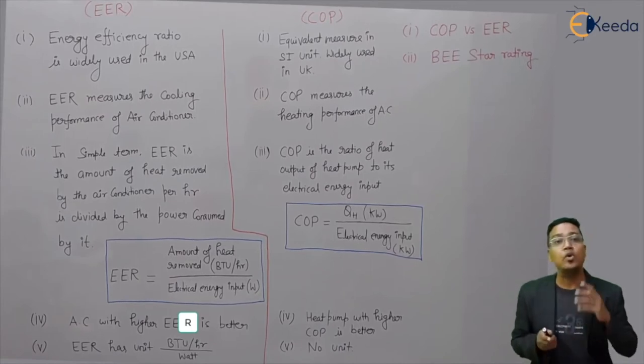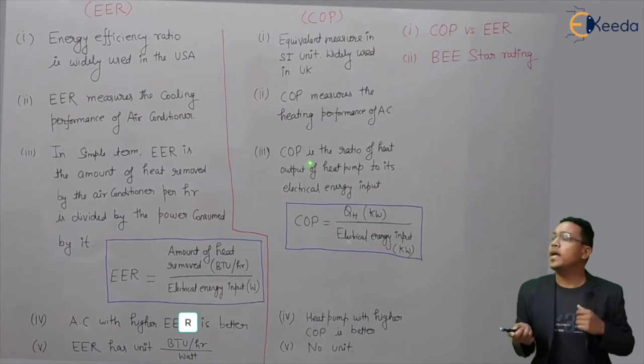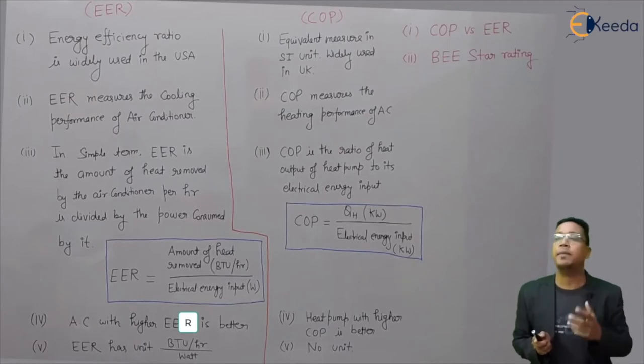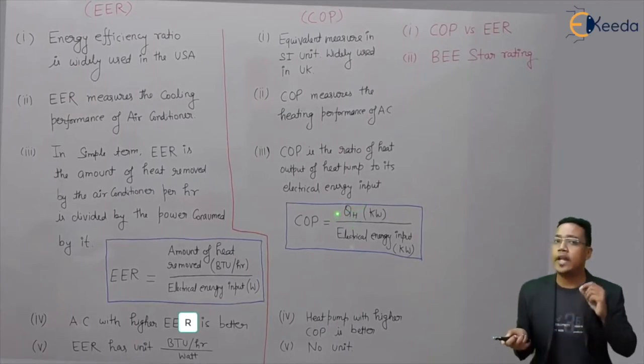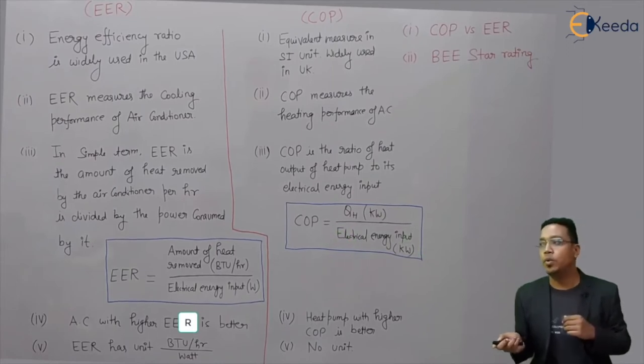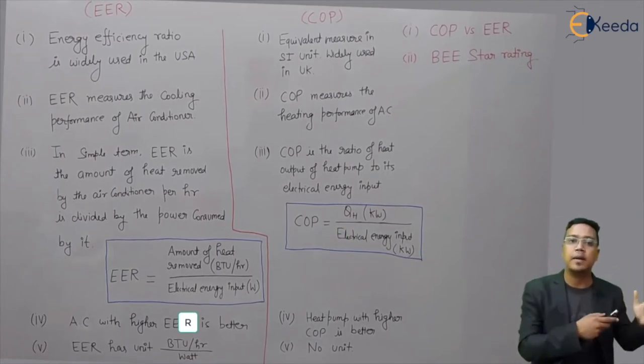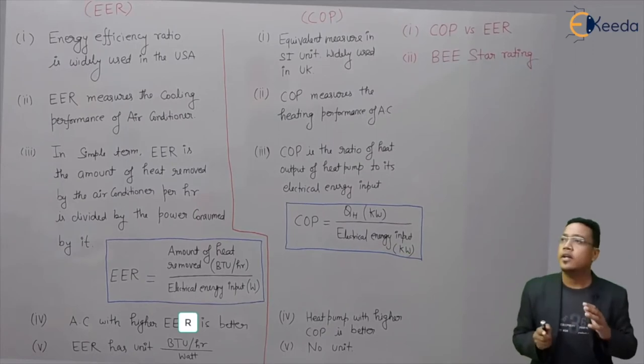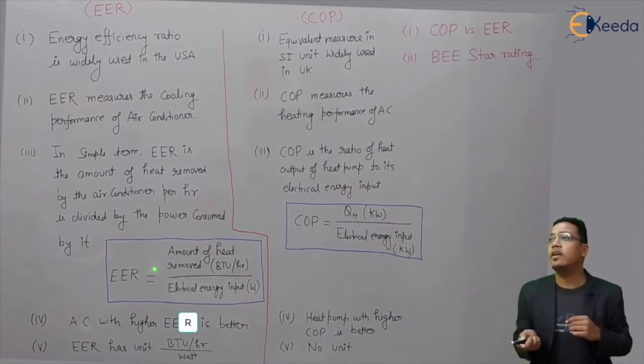If we talk about COP: COP is the ratio of the heat output of a heat pump to its electrical energy input. That means for a heating system or heat pump, the useful effect is QH, divided by the electrical energy input given to the heat pump. This is the difference between the definitions of EER and COP.